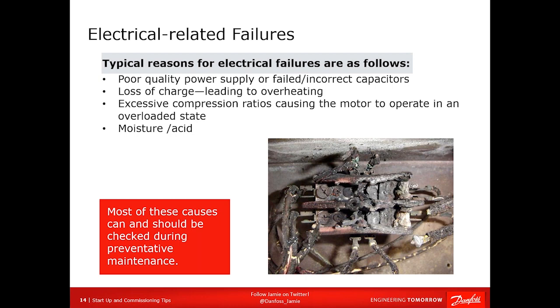And of course, moisture and acid. One of the good things about POE oil and HFC refrigerants is you cannot produce acid unless you have moisture. You can bake the crap out of that system and it'll fail, but it won't be highly acidic like back in the old days with chlorinated refrigerants and mineral oil. Oh my goodness, man, it would be so acidic it would actually cause burns on your hands and in your nose and your eyes. We don't get that anymore. So unless you have moisture, you cannot produce acid in an HFC POE system. So we've got to keep it dry.